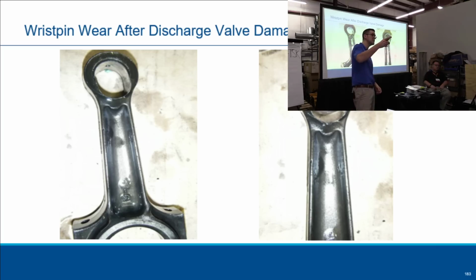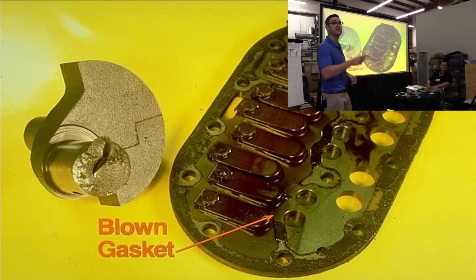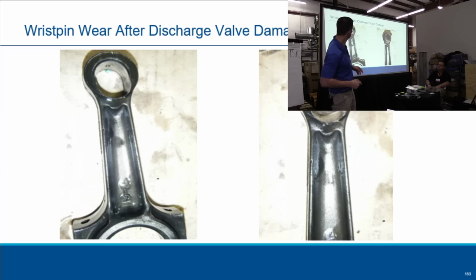Does that answer your question, Nick? Yeah, it does. So you go on Copeland Mobile, you put in your suction, your discharge, like we talked about, put your amps in, and then if that doesn't match up, you're outside the range, there's probably something wrong internally in the compressor. Okay. Trevor? Yes.